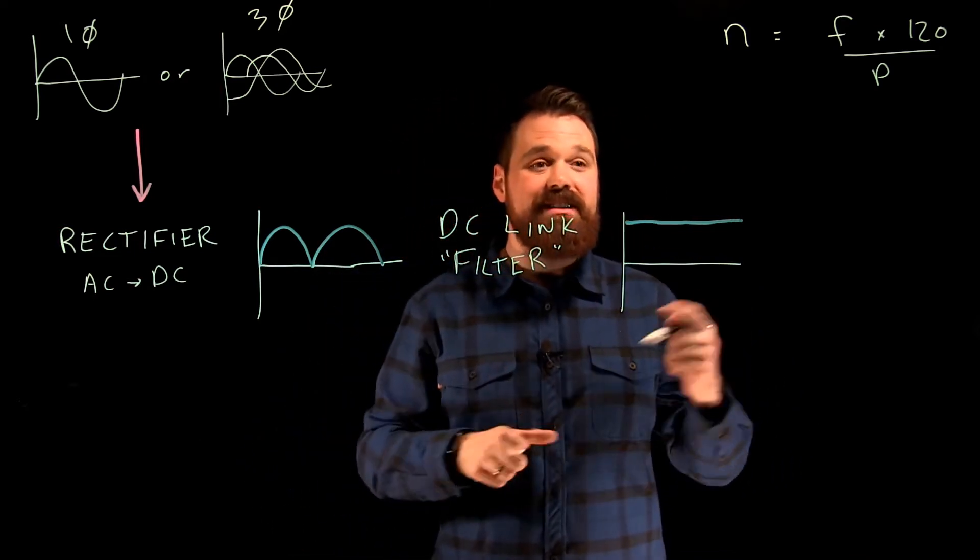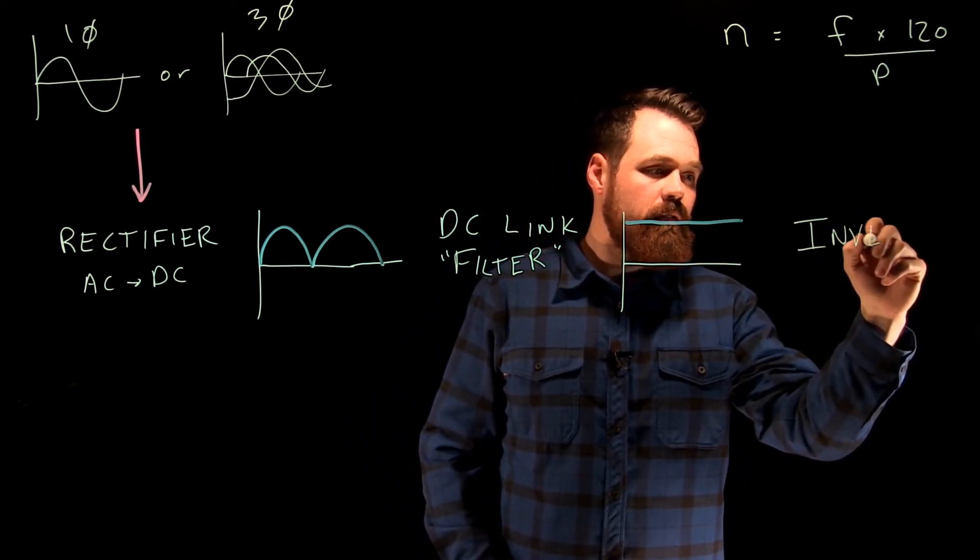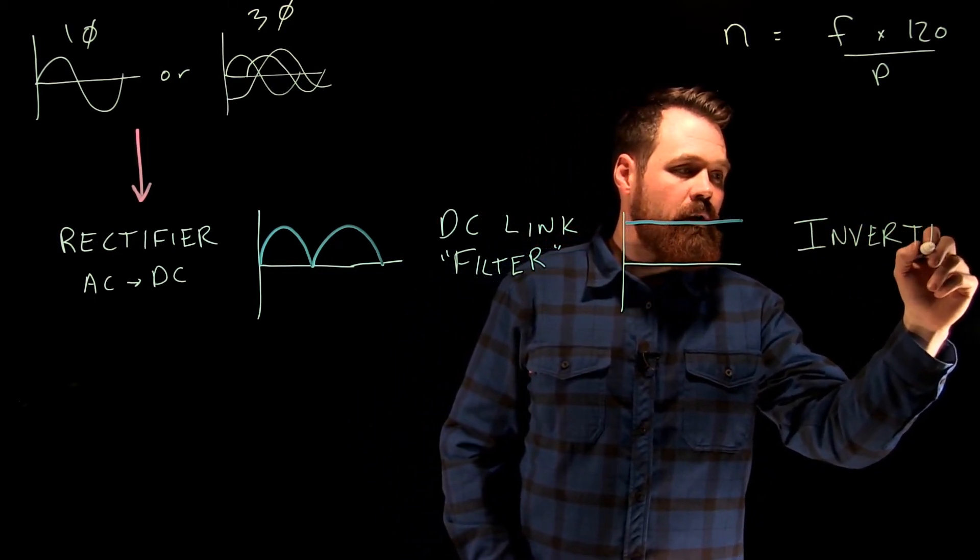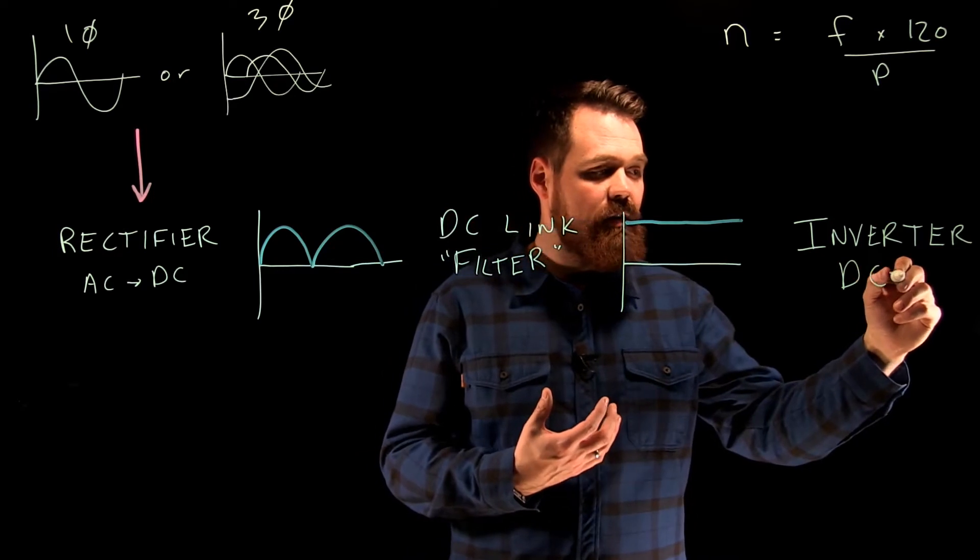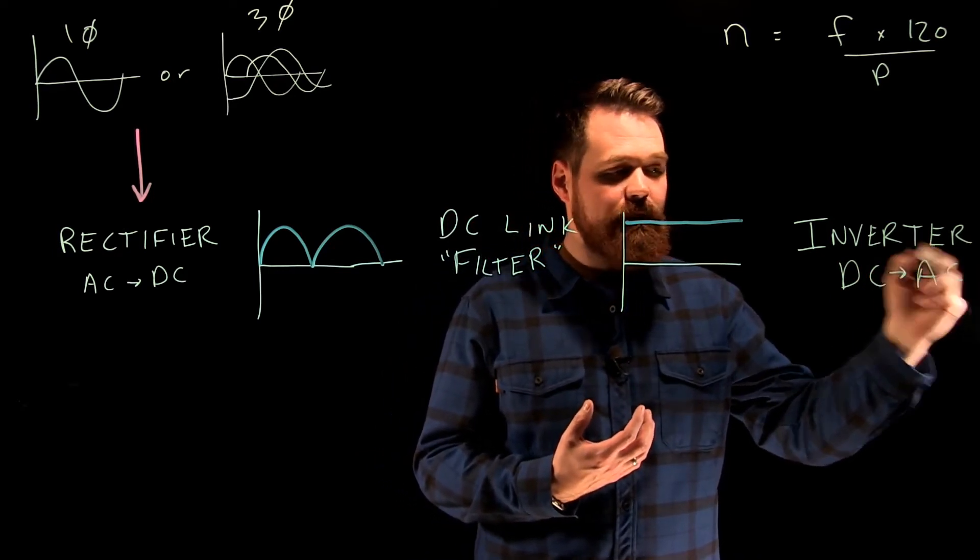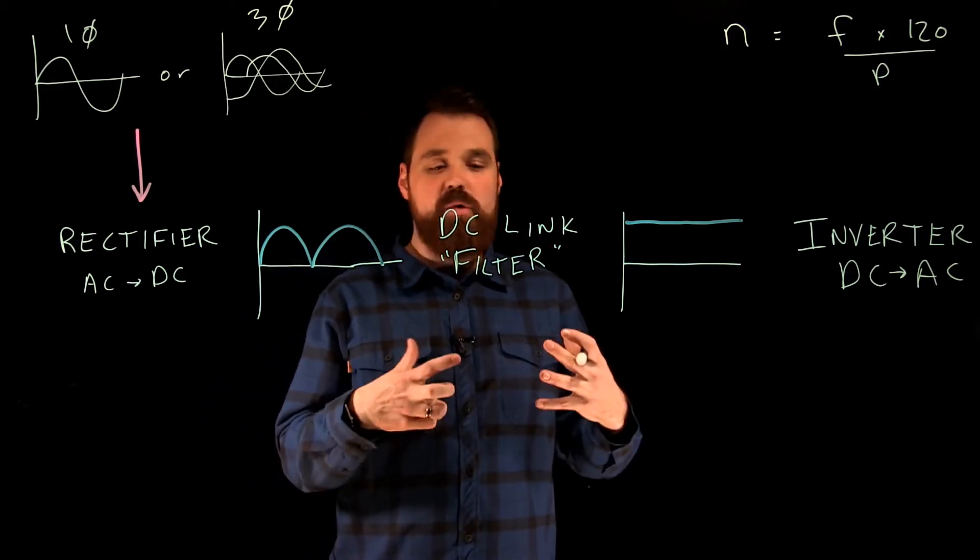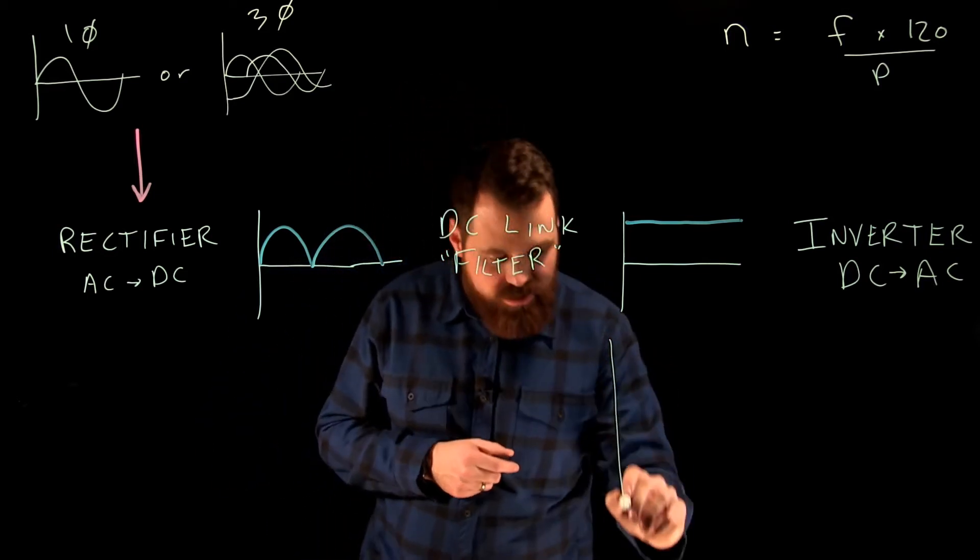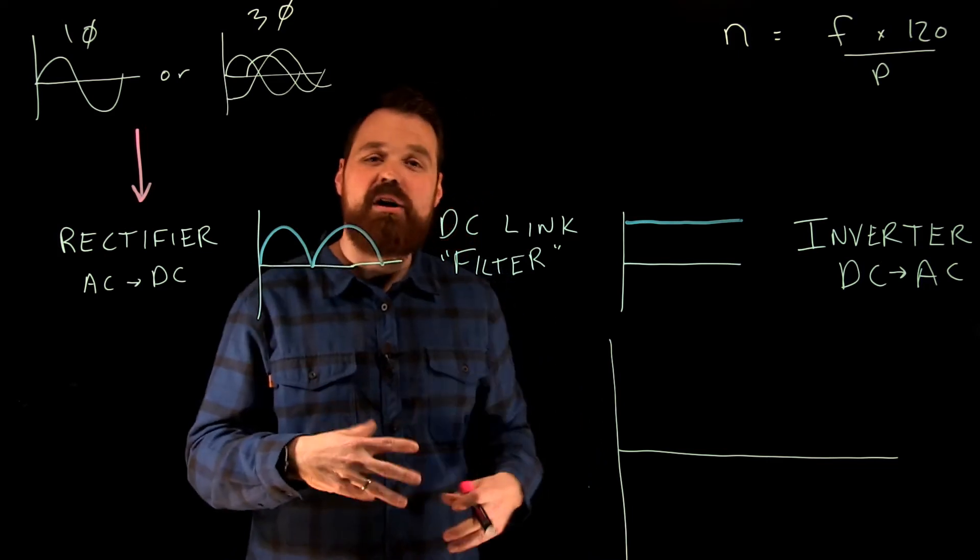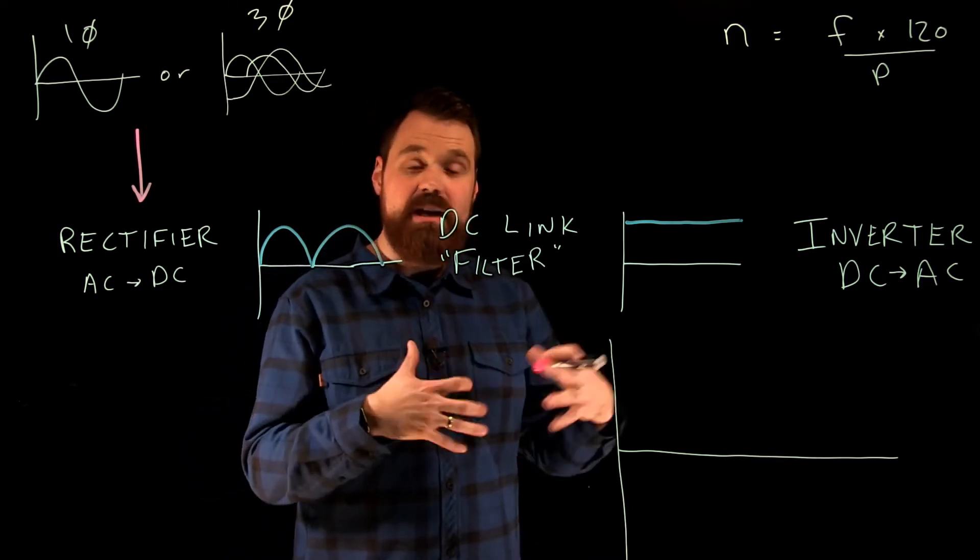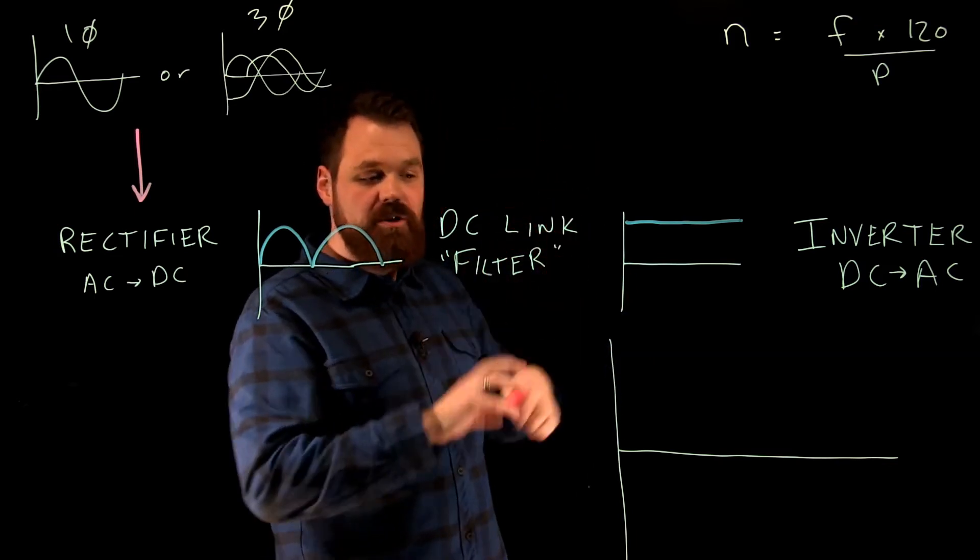Then we send it into the last part of the VFD, which is the inverter. What an inverter does is it takes DC energy and turns it into AC energy. The big trick with VFDs is when I do that, it will actually pulse the DC at different speeds for different lengths of time. It'll also adjust the DC voltage at which it's pulsing.